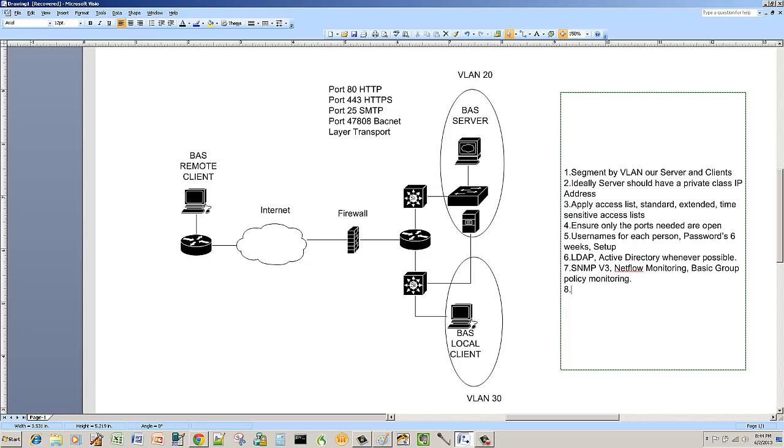The only thing I can say there is if your system's on LDAP and your server's on there, you've got to be careful. Let's say you're running a system that depends on Java and IT pushes out Java 7.0 and now nobody can log in. So you've just got to be careful. You've got to lay out the system requirements with the IT group and set update policies. And maybe that means monthly they review it and make decisions on what they're going to update.